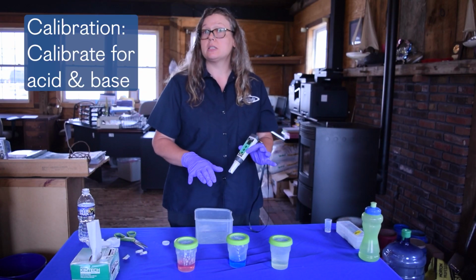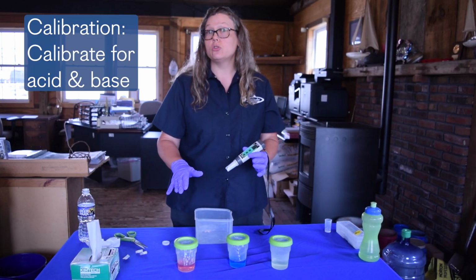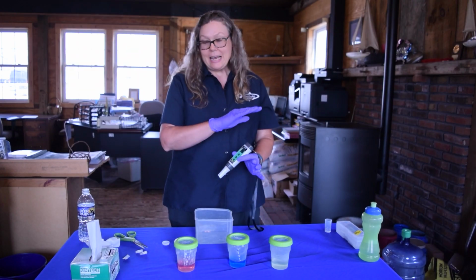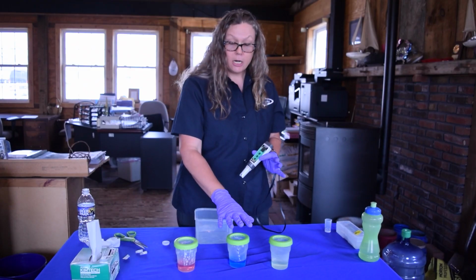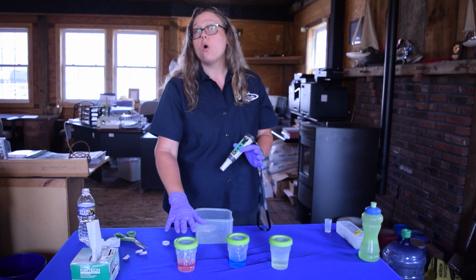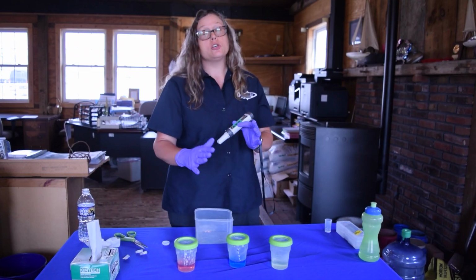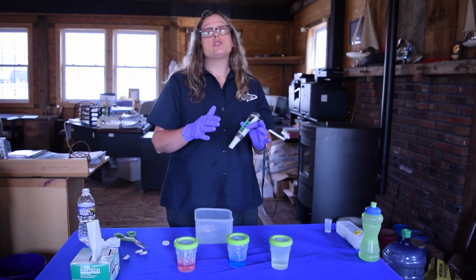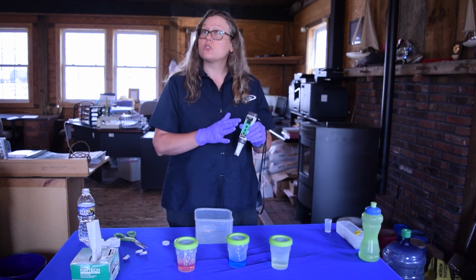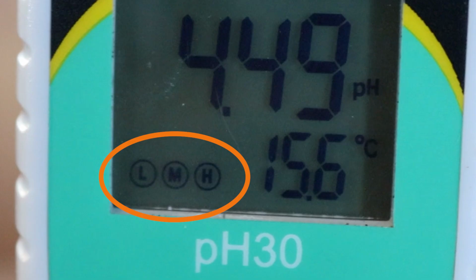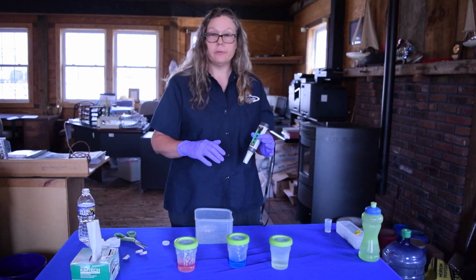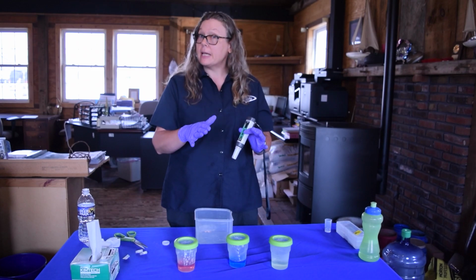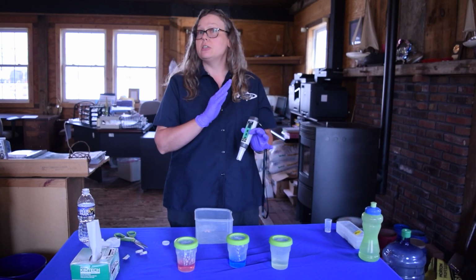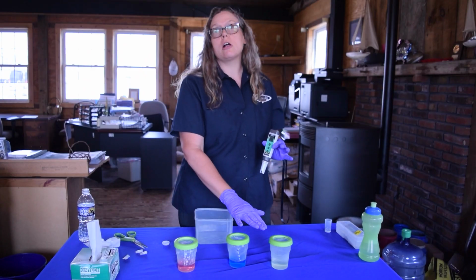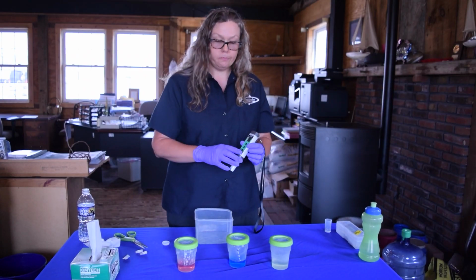We're going to repeat this process with the next two calibration solutions. It doesn't matter whether you calibrate your basic 10.0 solution next or your acidic 4.0 solution, just that both of them are calibrated so that at the end of the process on the screen, you have an L, an M, and an H in circles in the bottom left-hand corner of your screen. If you do not have all three of those symbols, your calibration process did not complete and you need to restart with the neutral solution.